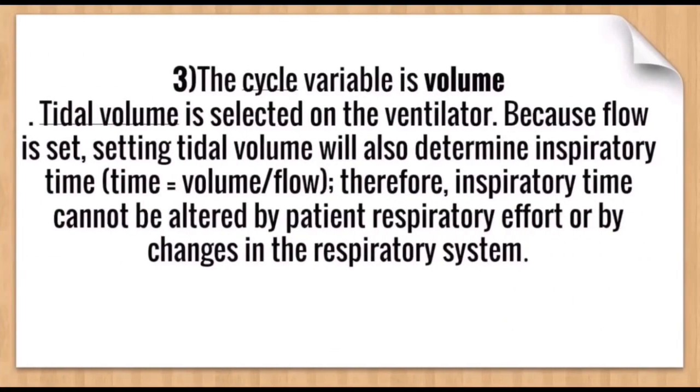Now the third thing is the cycle variable. The cycle variable is volume. That means on reaching a set tidal volume, the inspiration will terminate. So tidal volume is selected on the ventilator because flow is set. Setting tidal volume will also determine inspiratory time because flow is equal to volume divided by time. Therefore, inspiratory time cannot be altered by the patient's respiratory efforts or by change in the respiratory system.